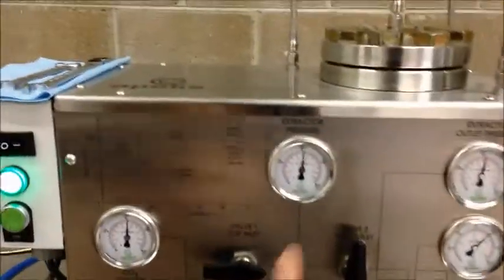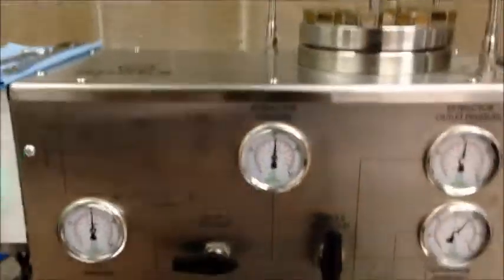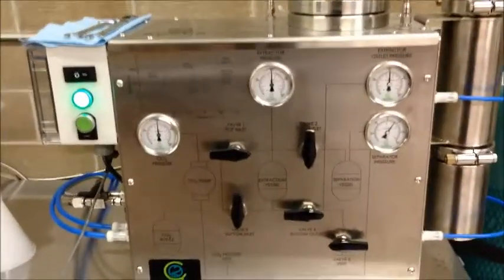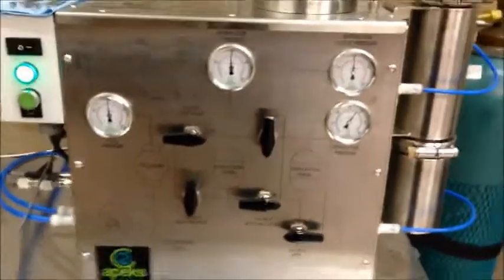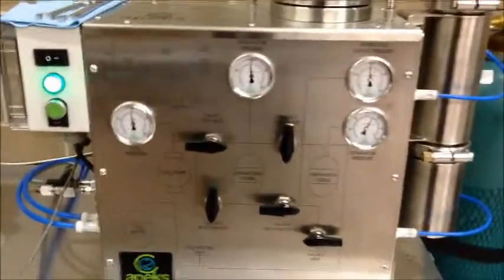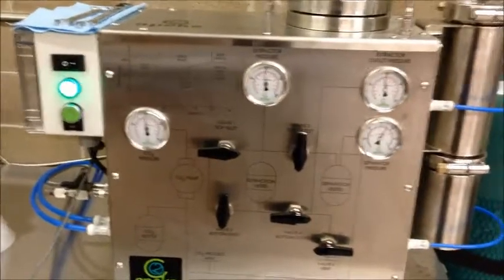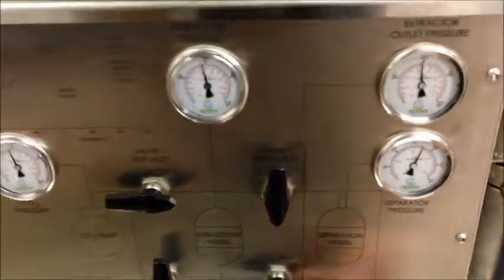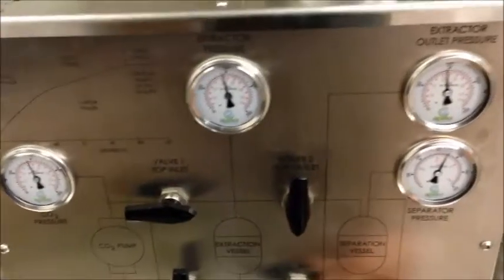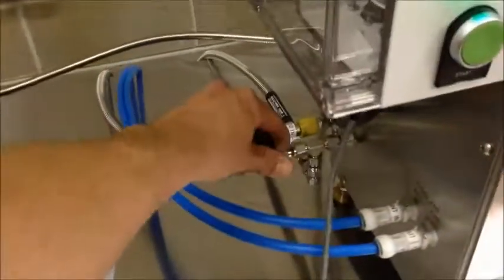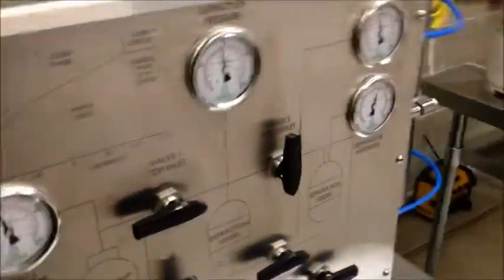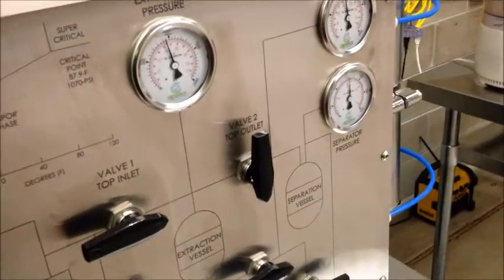What it'll do is slowly start pulling all this down, and like I said, the system will eventually shut off once it reaches around 200 psi or so. If it gets down to 200, say 205, 210 psi, and it's taking a long time to recover that last 5 psi, what you can do, help it out a little bit, just so you ain't sitting there letting the pump run all night. Open this, either open that one or open this one here, and bring it down the additional, yeah, that one there.